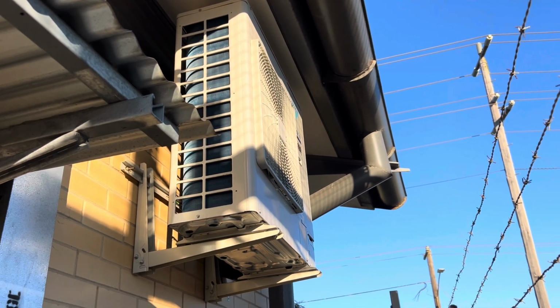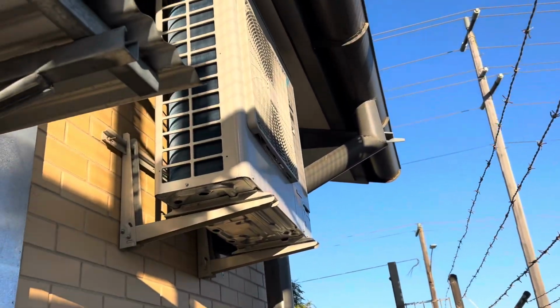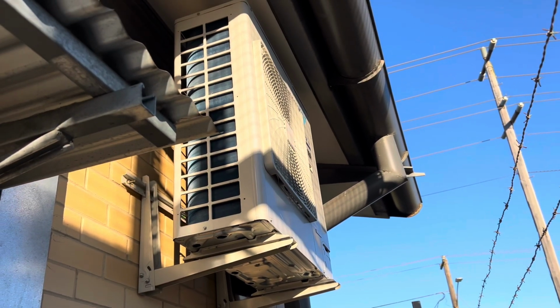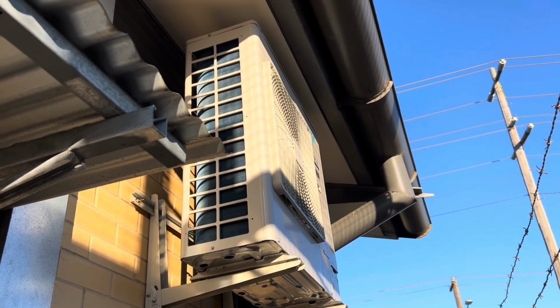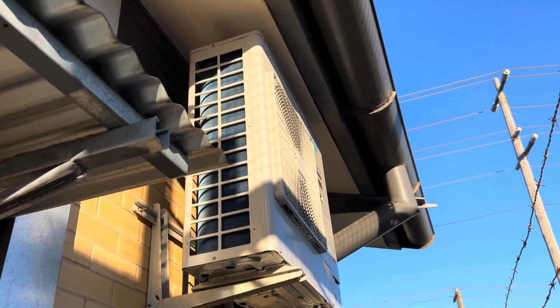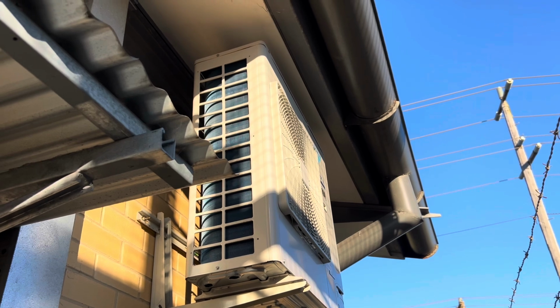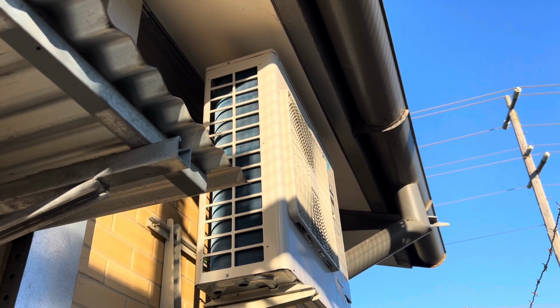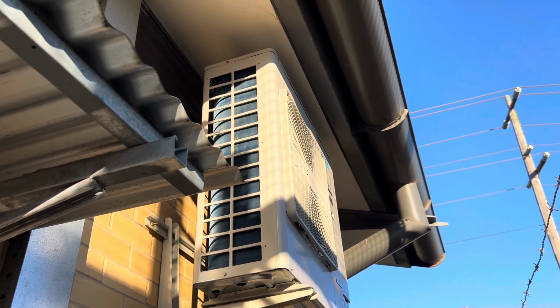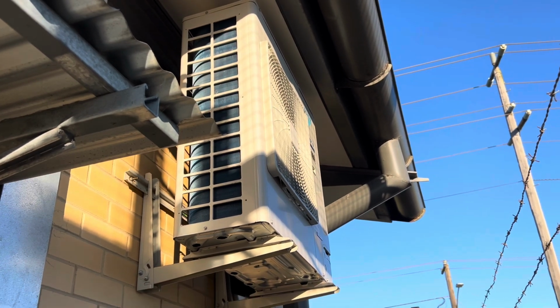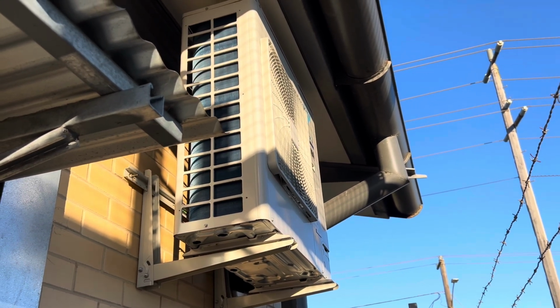So what I'm going to do, got all the gear, we can plug in our service checker, go over the data, have a look at it, and we'll disconnect it from the BMS system so I can run it independently. Basically they're saying the rest of the building is sitting at 20 degrees, and these two rooms are sitting at 17 degrees. So we'll jump into getting the service tool plugged in.